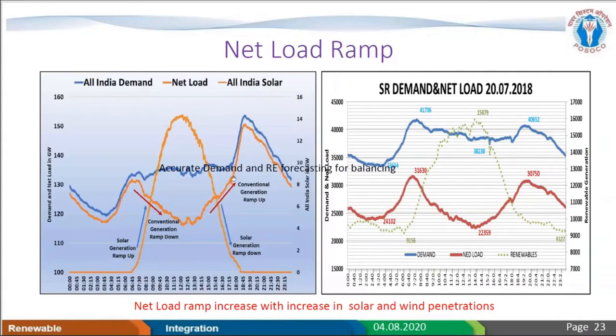Now what does that mean? It means solar has to be accommodated anyway. The demand variation plus the solar variation is making my requirement from conventional generation come down. If you see this rate, this is the demand plus solar requirement, which is forcing the ramp rate requirement to be higher, because this much of generation gap is being filled by solar, meaning my thermal generator has to go down.